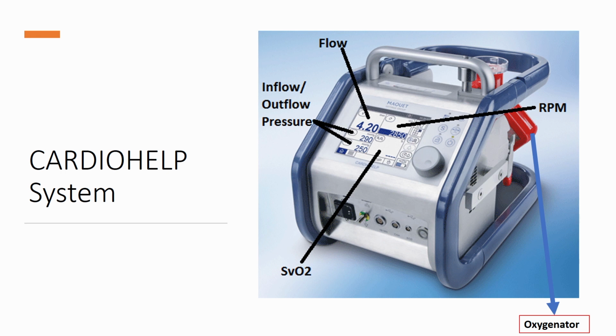There's just some basic metrics to go over. There's the flow right there. So you can think of it as the artificial cardiac output. And remember, the cardiac output in an individual is usually about 6 to 8 liters per minute. And we control the flow by adjusting the RPMs of the machine. That's a centrifugal pump in this machine. As you put up this little dial, you put up the RPMs to adjust the flow of the machine. And if we have someone on ECMO, daily we'll do flow checks and turn down the flows and see how the hemodynamics adjust. We turn down the flows by adjusting the RPMs.